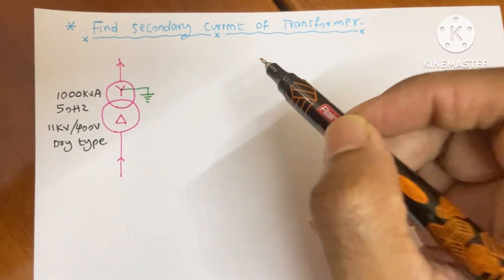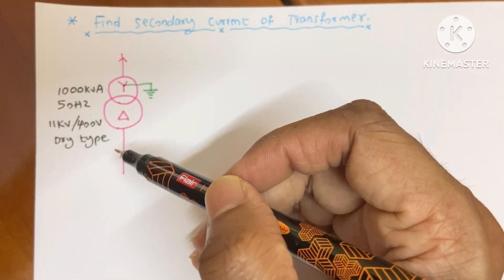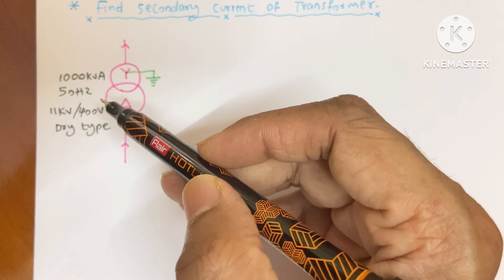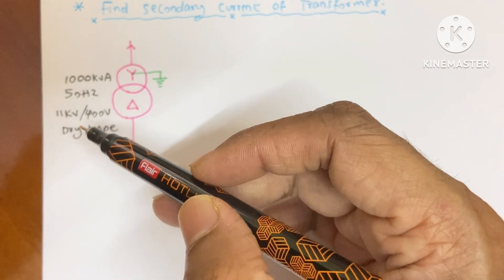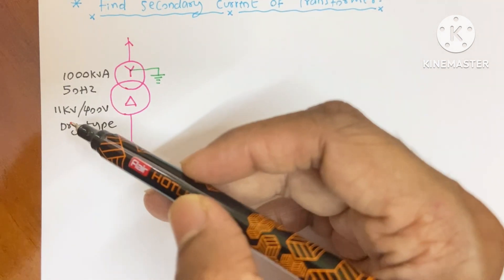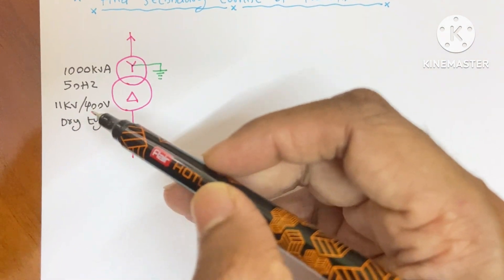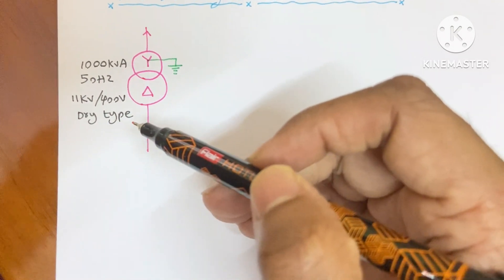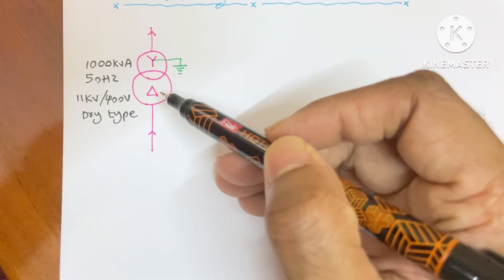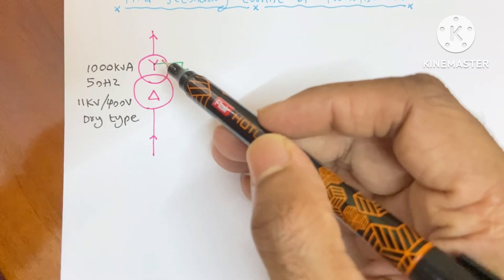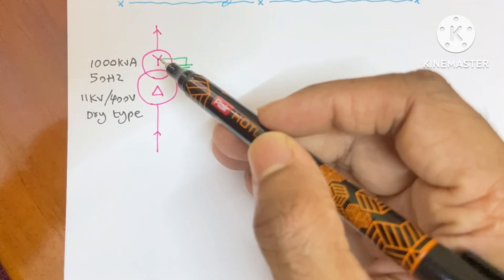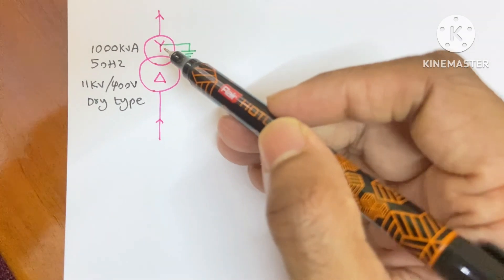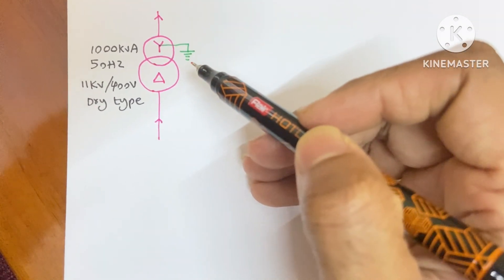Here we have a distribution transformer of 1000 kVA, 50 hertz, with a voltage of 11 kV on the primary side and 400 V on the secondary side. It is a dry type transformer. Its primary side is delta connected and the secondary side is star connected, meaning its neutral is already grounded.